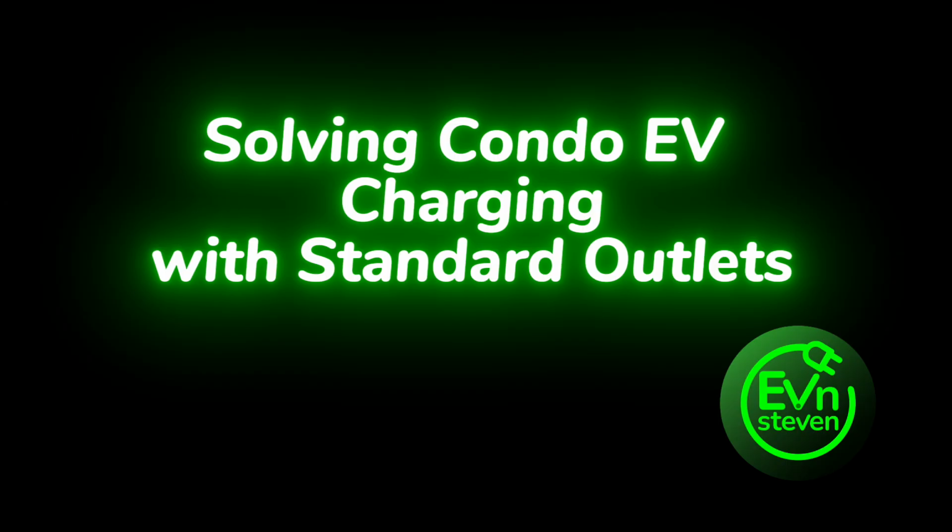The code dictates that any device drawing power for more than 3 hours continuously cannot pull more than 80% of the circuit's rated maximum capacity. So for a standard 20-amp breaker, 80% means the vehicle cannot pull more than 16 amps of power. Correct. And modern EV charging cables are designed around this exact limitation. The mobile connectors provided by manufacturers like Tesla or Kia are UL-approved devices engineered with built-in safety margins. Oh, that's good to know.